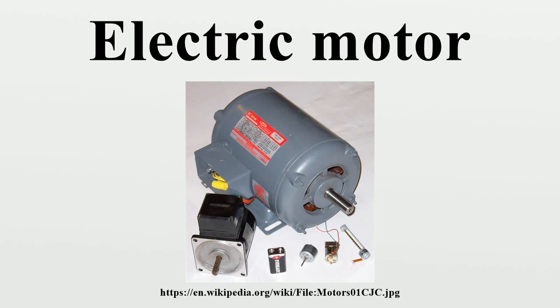Stator. The stator is the stationary part of the motor's electromagnetic circuit and usually consists of either windings or permanent magnets. The stator core is made up of many thin metal sheets, called laminations. Laminations are used to reduce energy losses that would result if a solid core were used. Air gap.